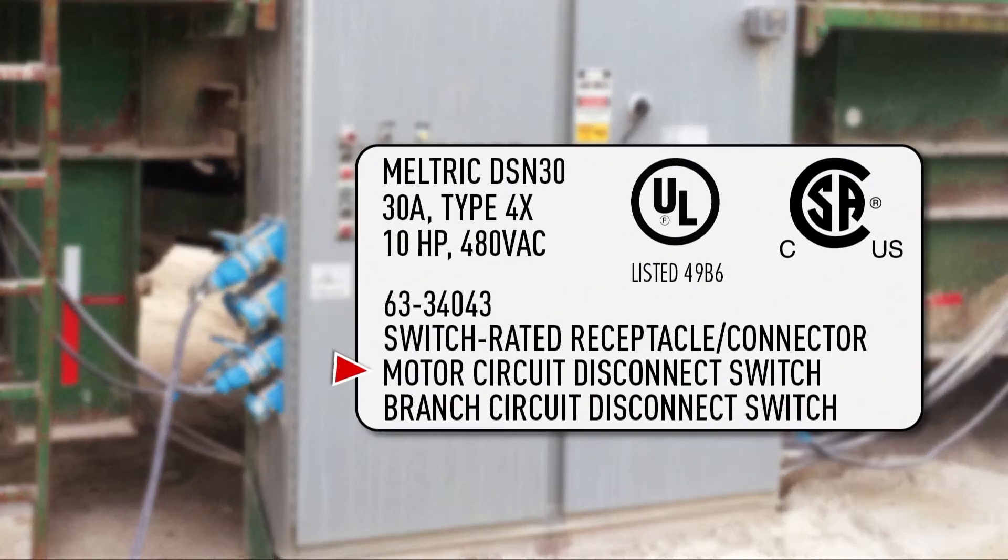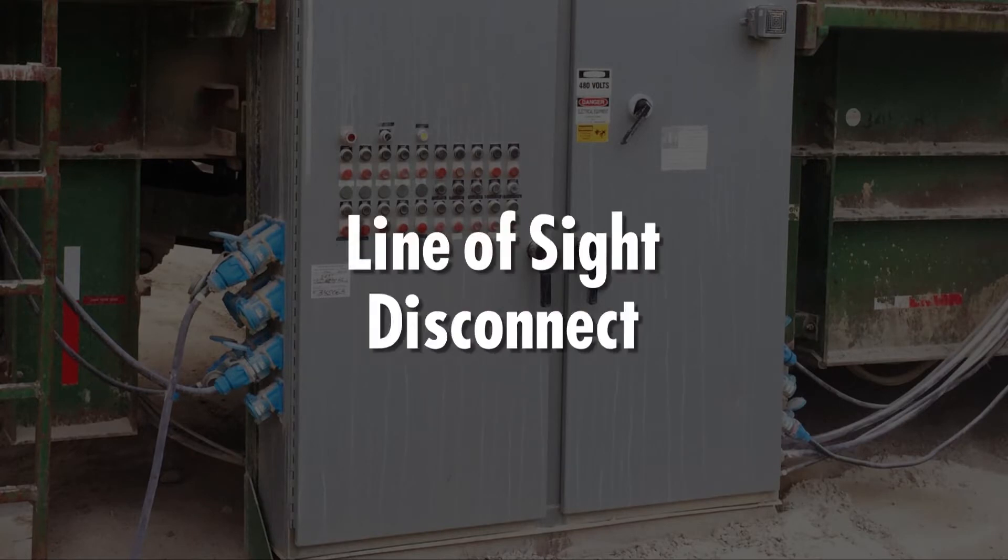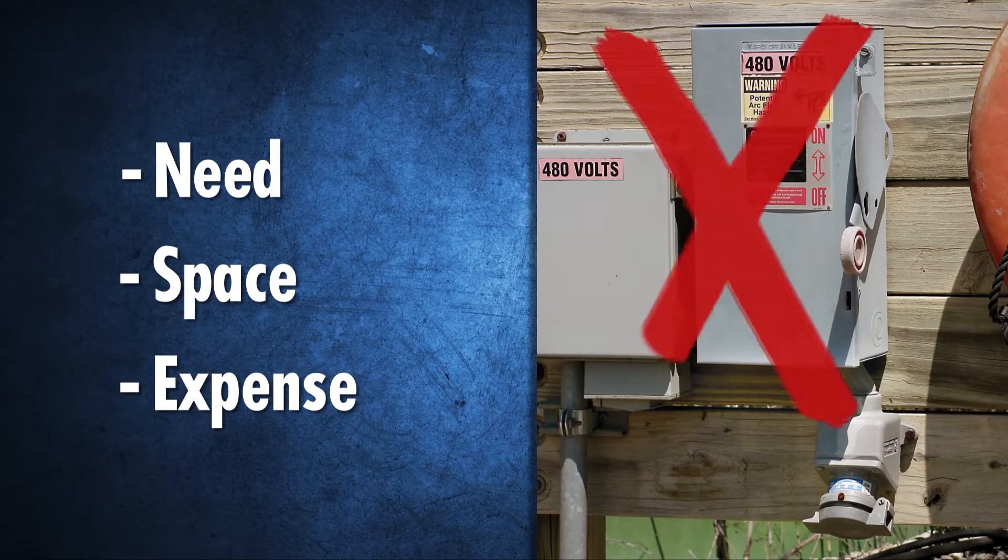UL and CSA motor circuit and branch circuit disconnect switch ratings shown on the device label allow them to function as the code required line-of-sight disconnect, so the need, space, and expense of a separate non-fused disconnect switch is eliminated.